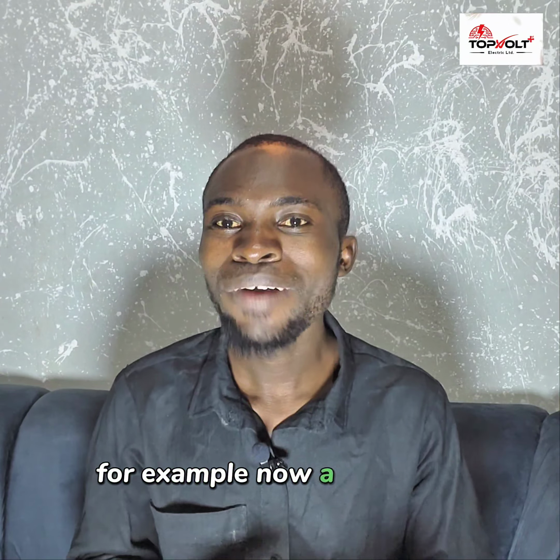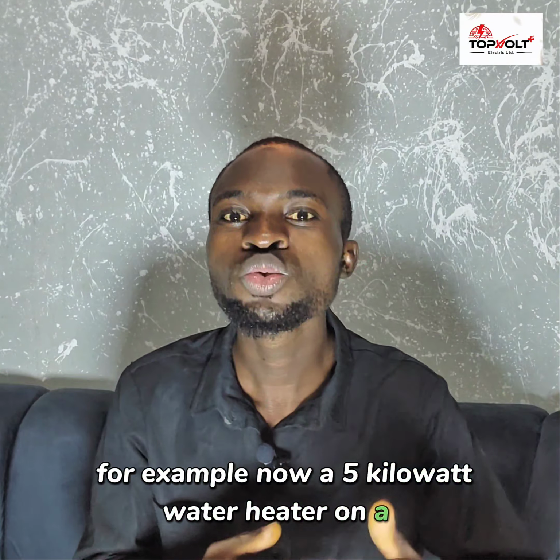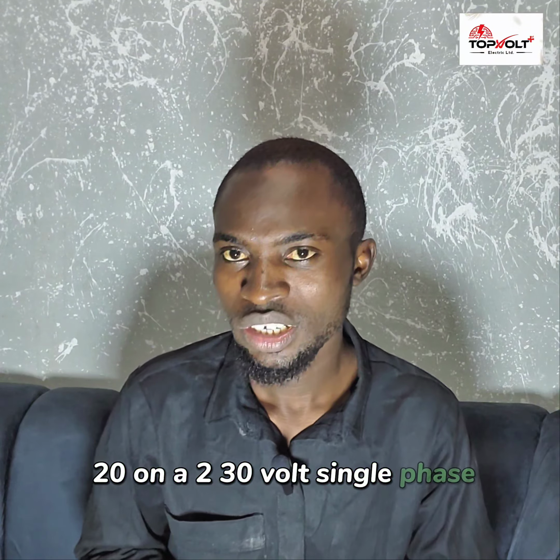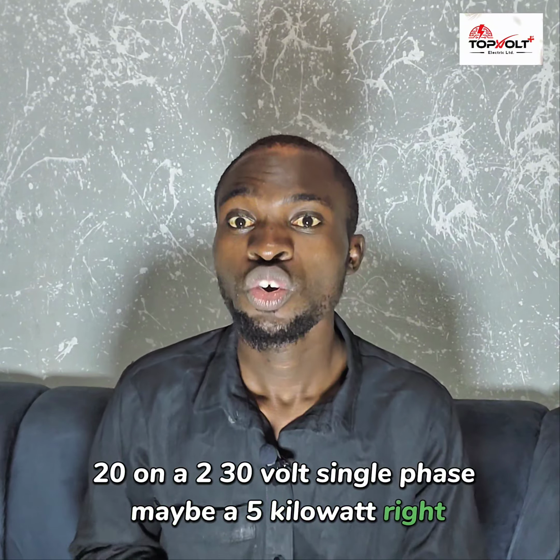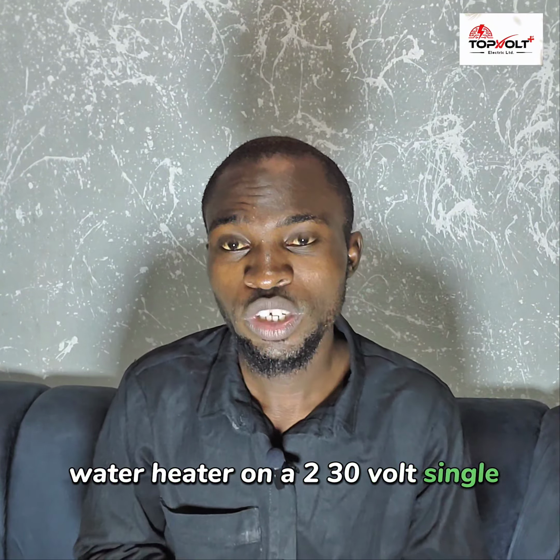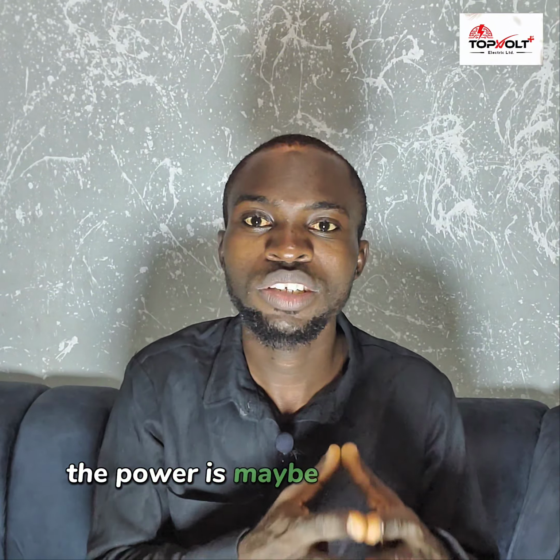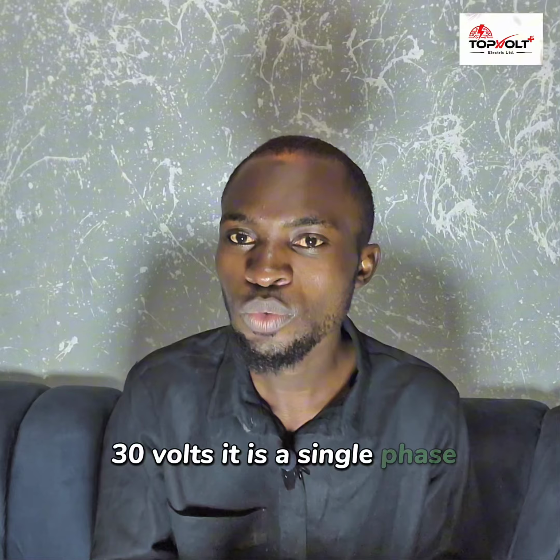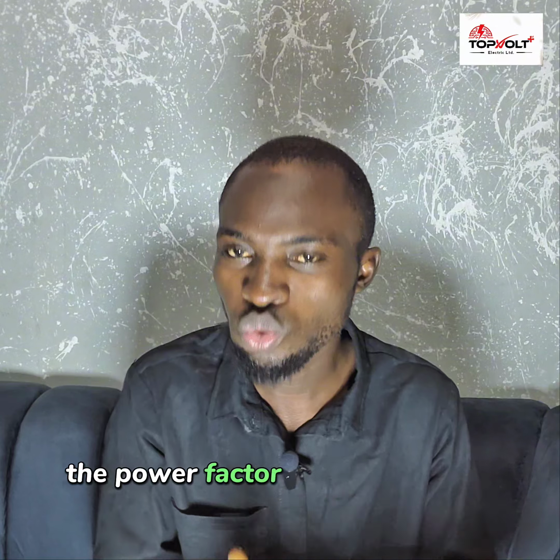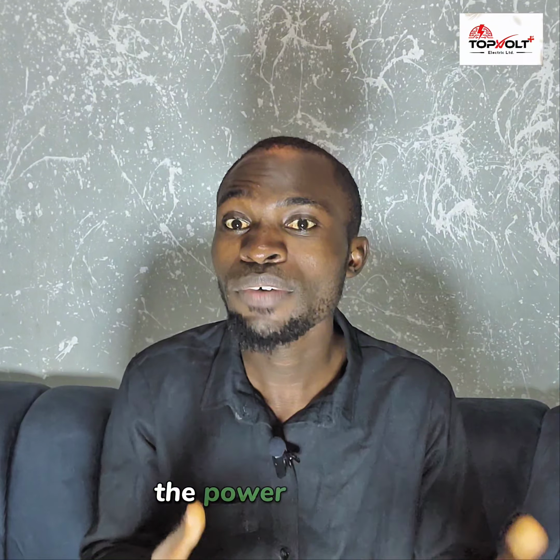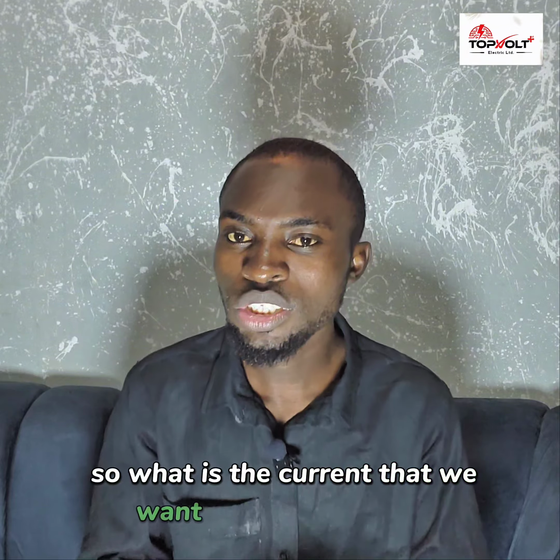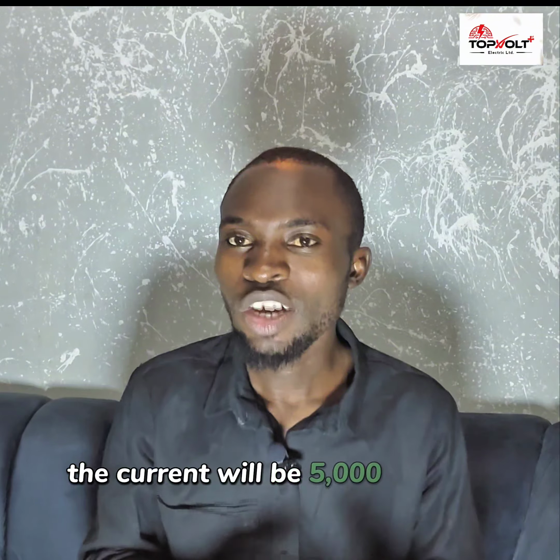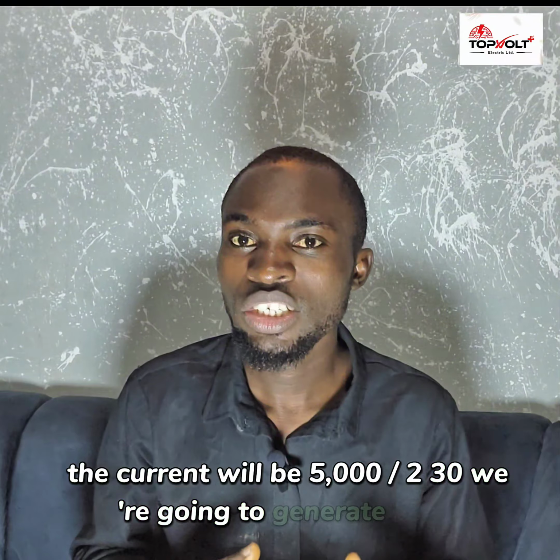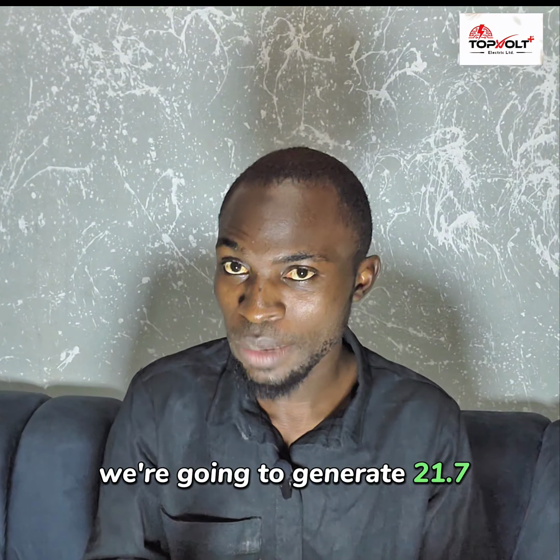For example, now a 5 kilowatt water heater on a 230 volt single phase. The power is 5 kilowatts, right? The voltage is 230 volts, it's a single phase voltage, and the power factor is 1. So what is the current I want to generate? The current will be 5,000 divided by 230. We're going to generate 21.7 amps, right?